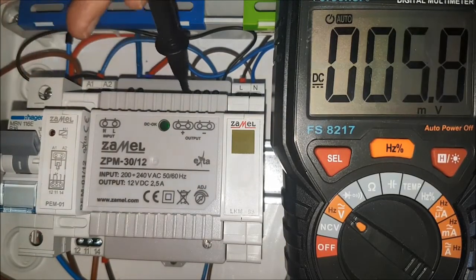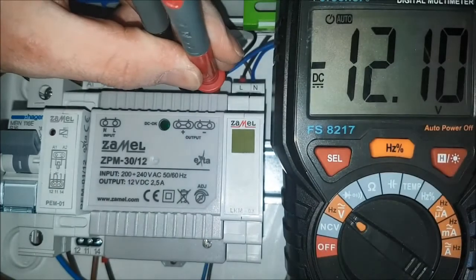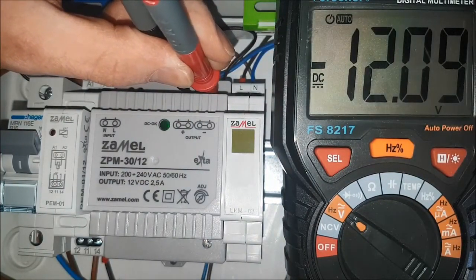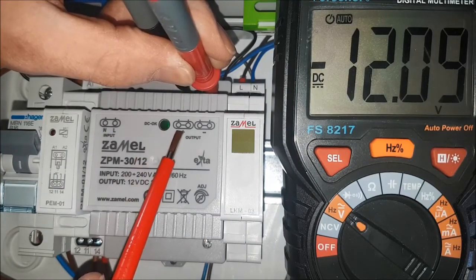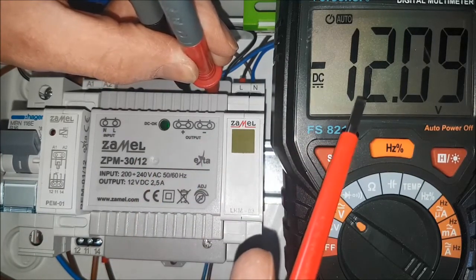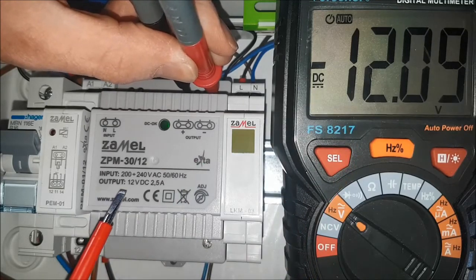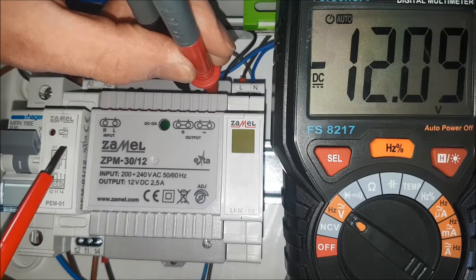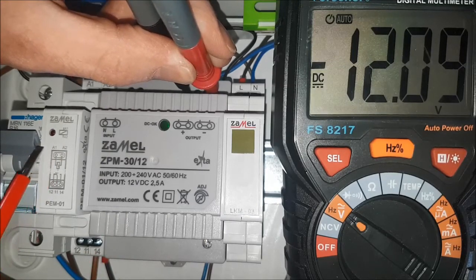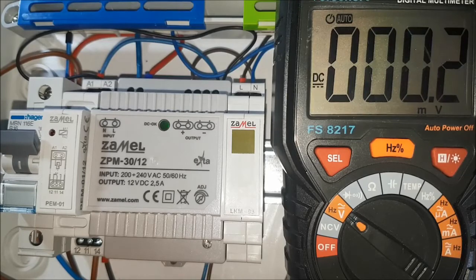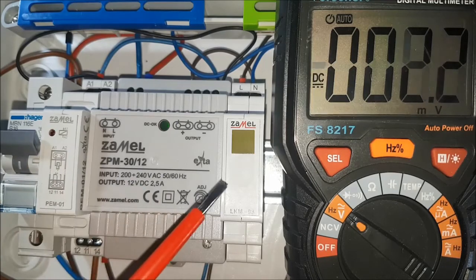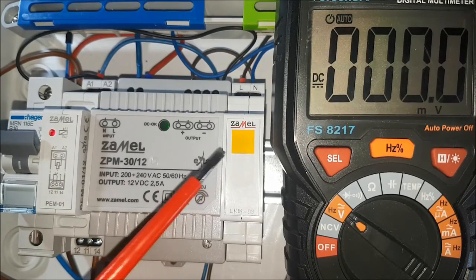Provide the power supply voltage. Check the value of voltage supplied by the ZPM30-12 power supply. It is consistent with the parameters on the housing and is 12 volt DC. The minus symbol indicates the voltage polarity as shown in the power supply diagram. By shorting the push button we close the relay coil circuit PEM-01, 012. This causes the relay to be activated, which is indicated by the red LED lighting up and the LKM03 power supply indicator.